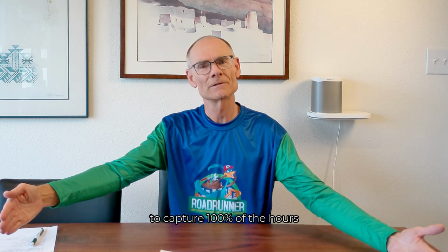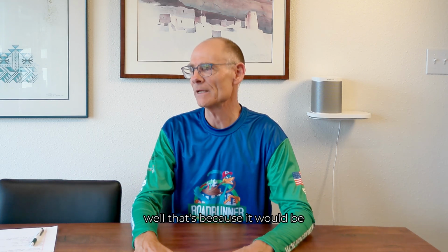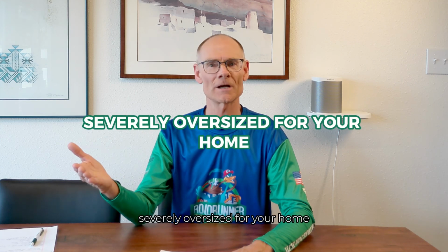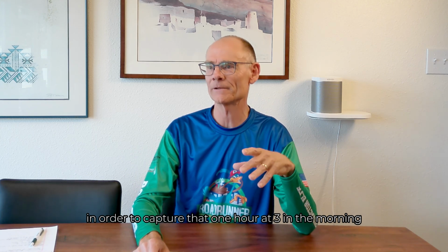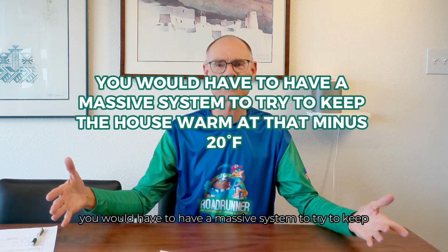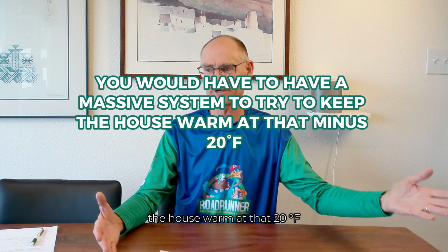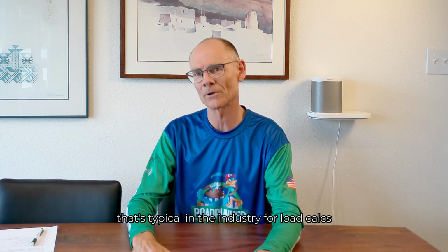Why don't we try to do a load calculation to capture 100% of the hours? Well, that's because it would lead to an HVAC system that would be severely oversized for your home. In order to capture that 1 hour at 3 in the morning, 16 years ago, when it got to minus 20 degrees in White Rock, you would have to have a massive system to try to keep the house warm at that temperature. So you just don't do that. You use the 98th percentile. You capture 98% of all the temperature hours. That's typical in the industry for load calcs.